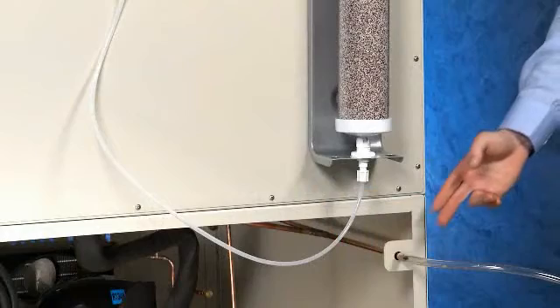The demineralizer system must be plumbed into its own water source and regulated to 30 psi. During operation, city water passes through the filter and is cleaned on its way to the steam generator. The steam condenses in the chamber and is then drained here in the back of the chamber. Polytubing can be used to direct water to a designated drain area such as a lab sink or floor drain.